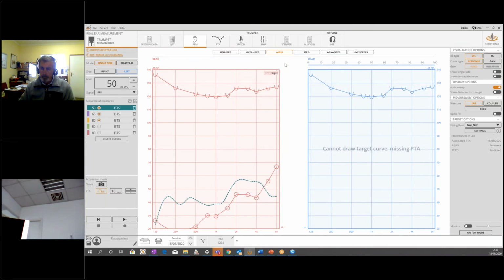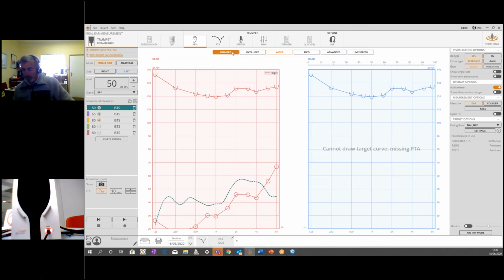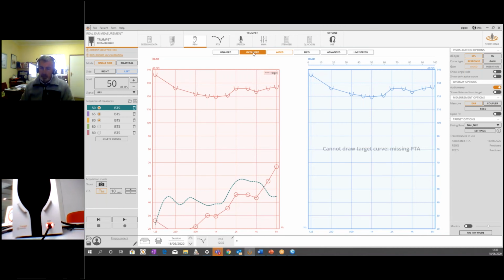Okay, aided. So, the audiologist or the hearing care professional must acquire the unaided measurement, so without the hearing aid, in order to get the natural amplification of the ear canal. The occluded one with the hearing aid inserted and turned off, okay? The first curve and the second one match if the patient is wearing an open hearing aid, surely. Then we want to acquire an aided measurement, okay? So to get the amplification at the eardrum, amplification provided by the ear canal itself and the hearing aid.